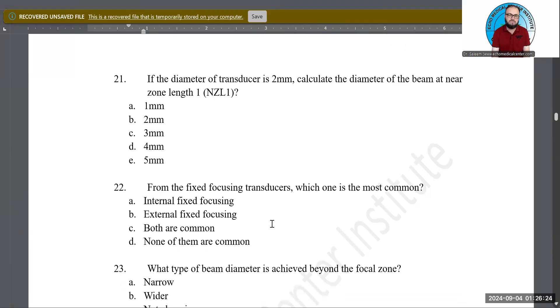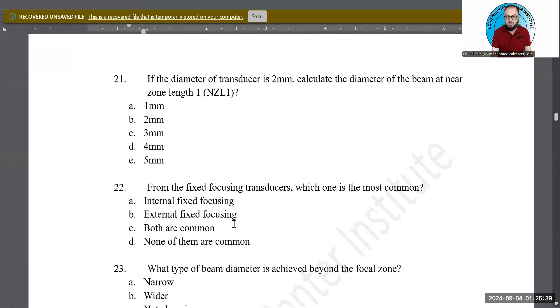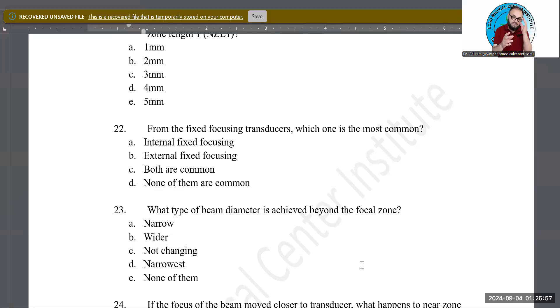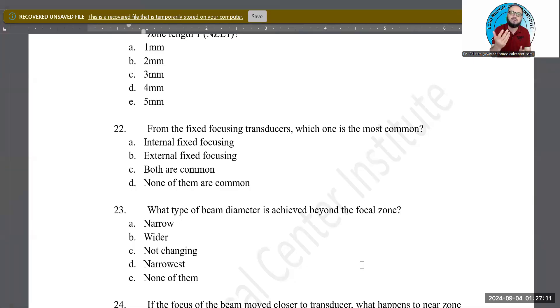Next question: from fixed focusing transducers, which type is most common — internal fixed focusing, external fixed focusing, both, or none? Internal fixed focusing is the most common. The difference: with internal fixed focusing, the PZT crystal itself is curved in shape. With external fixed focusing, an additional curved lens is placed in front of the PZT — an extra element inside the transducer.